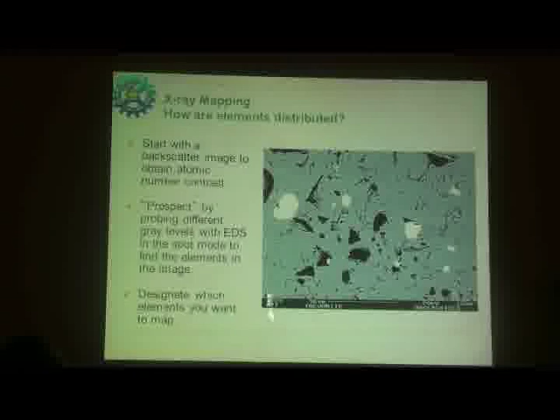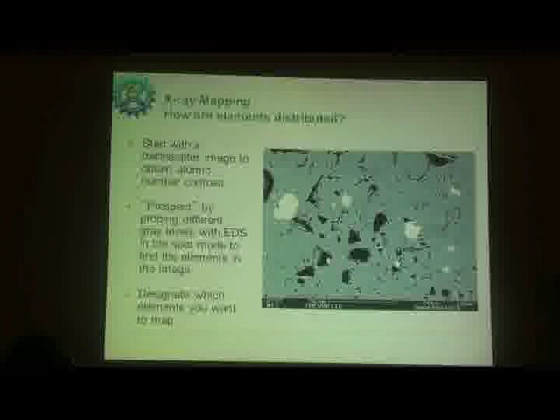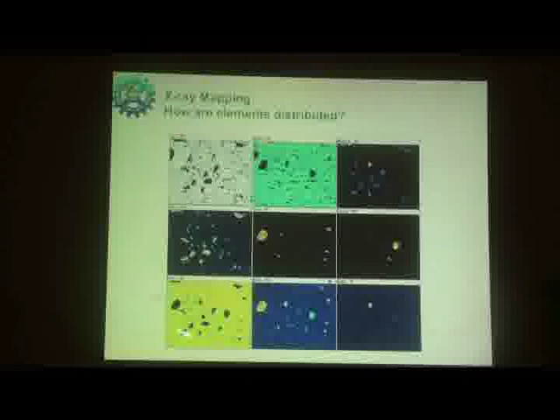You want to do the X-ray dot mapping, and the X-ray dot mapping means the elemental distribution in that particular matrix. Suppose this frame contains a lot of elements. How those elements are distributed in this particular matrix, whether they are uniformly distributed or isolated in some corner, can be determined at the same time by this X-ray dot mapping. Whatever X-rays come from these particular locations will be stored and put into a separate frame for each element, and those frames can be recorded. Suppose you have silicon, sulfur, antimony, iron, nickel, and arsenic. How all these elements are distributed can be done with EDS.